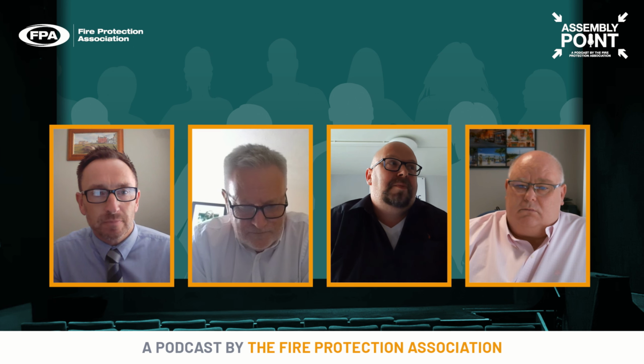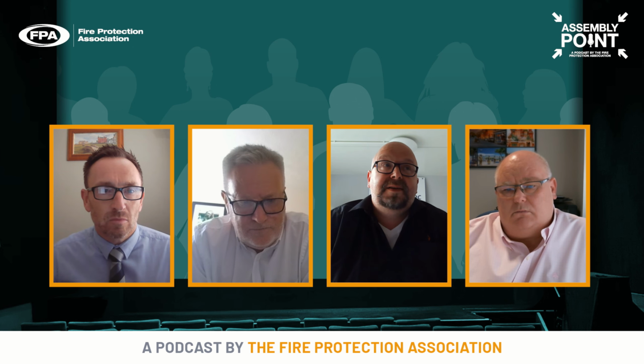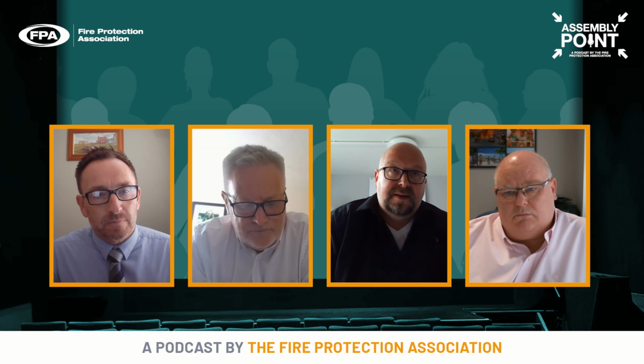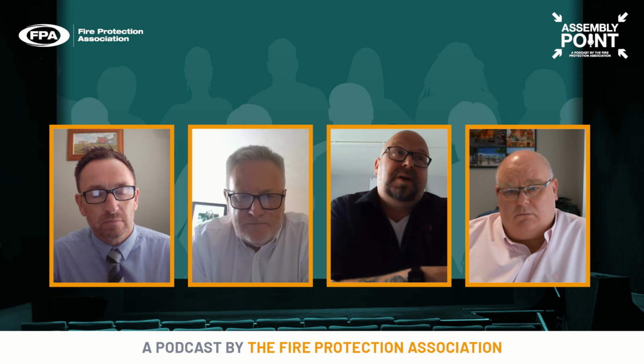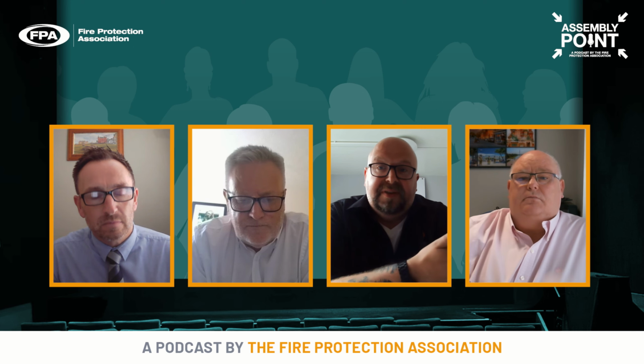Well, I've done quite a bit of work on this. I work a lot with the third-party accreditation bodies through the training courses that we have running. And the feedback is that historical residential and domestic installation companies don't really understand the commercial market. When it comes to protecting the commercial side, they're just designing it as if it was a residential job. So you're getting retail with plastic pipe, spaced at 25 square metres and calculated in 4 heads, which is not right, because if you look at Table 4, it says it all has to be spaced to BS EN 12845. So the biggest challenge is going to be to train these people in that.